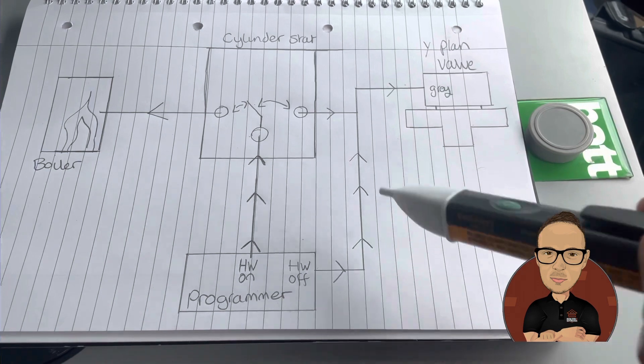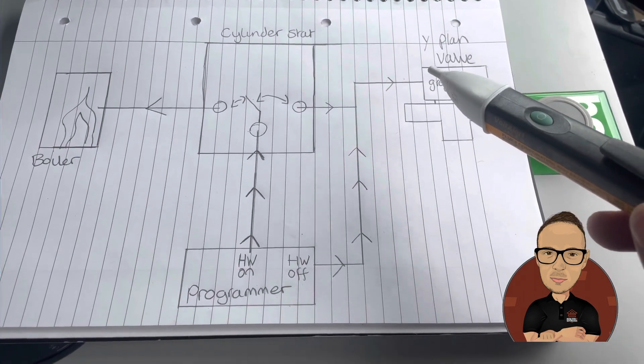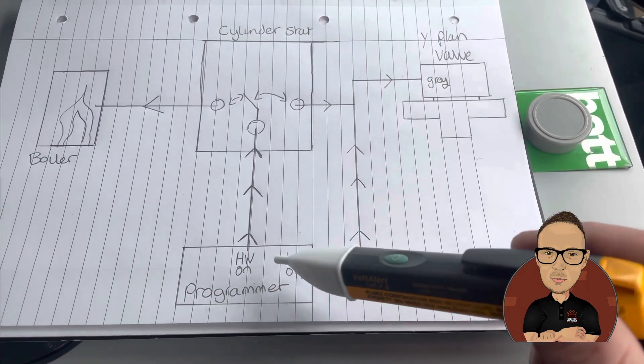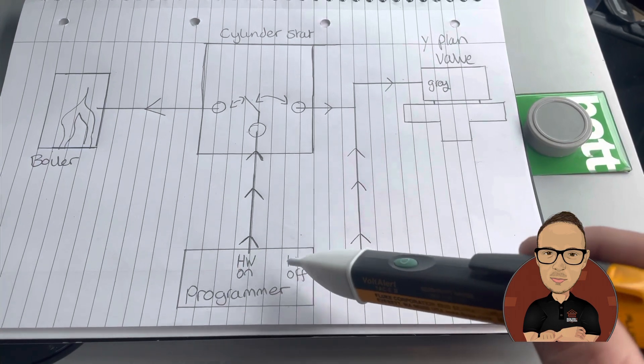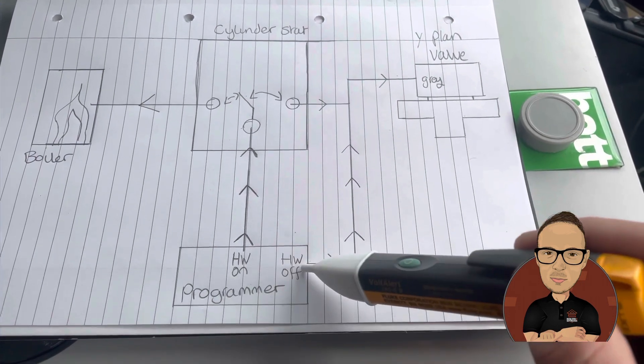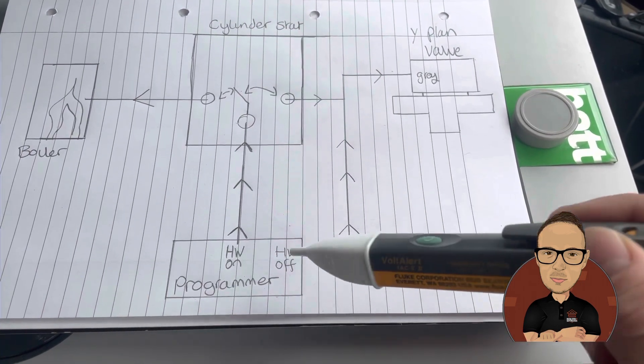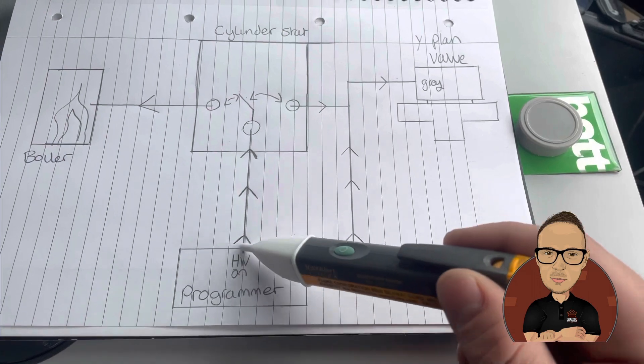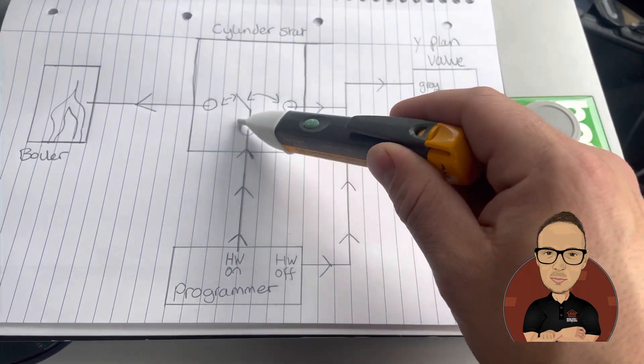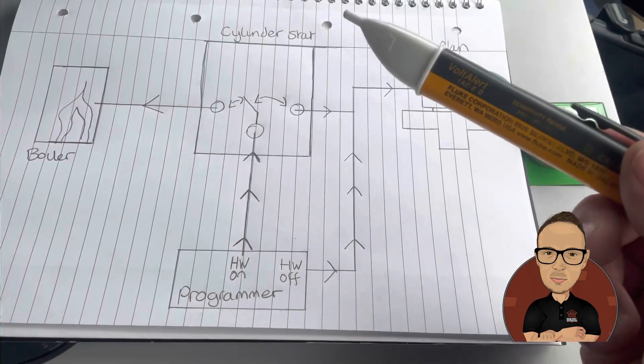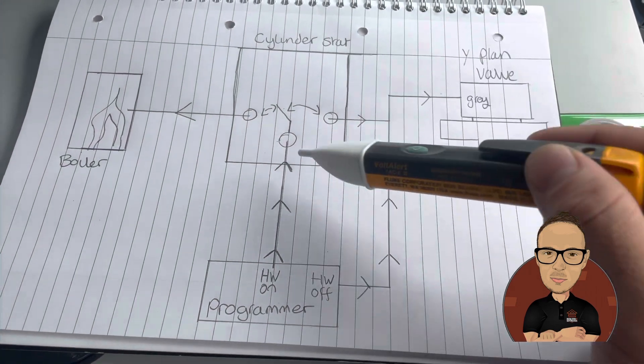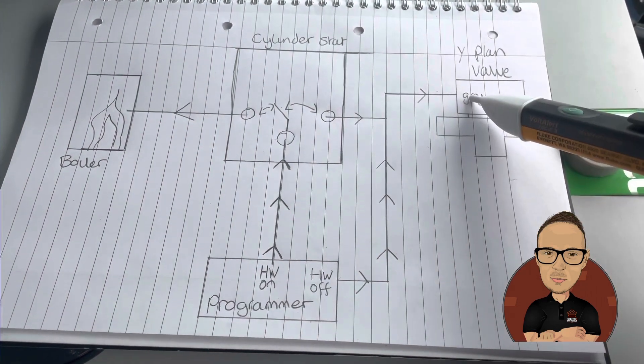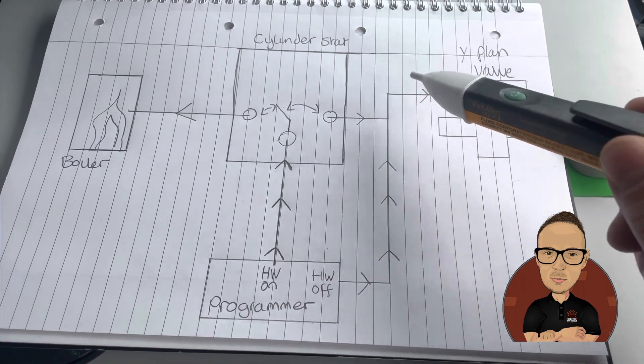The reason why I think people find it a little bit confusing, which is what I found confusing, the programmer won't send 240 on hot water on and hot water off at the same time. So you're either going down this channel of wanting hot water and then you fire your boiler if you want the temperature. If your temperature is achieved, it goes and closes the Y-Plan valve, giving power on grey.